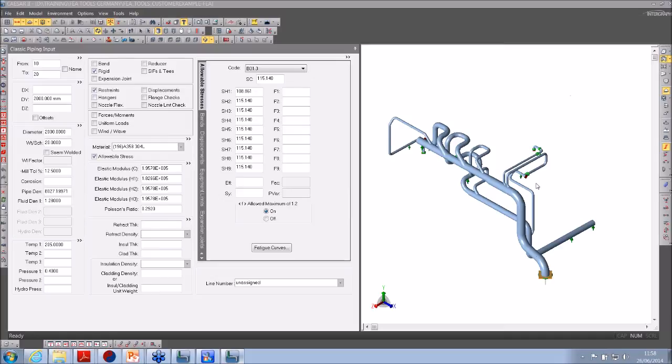Yeah, because of course with the comparison tool, they don't have to be a before and after translated file. They can just be any CAESAR II files. Exactly. And so the comparison tool and the PRGIK calculator are the tools here that we end up using the most, because as you pointed out, Steve, what you really want to know about flexibilities is the K factor. So you go into the PRGIK tools, check the K factors. If they're all low values, then there's no reason worrying about extra flexibility in the model. Yeah, exactly.